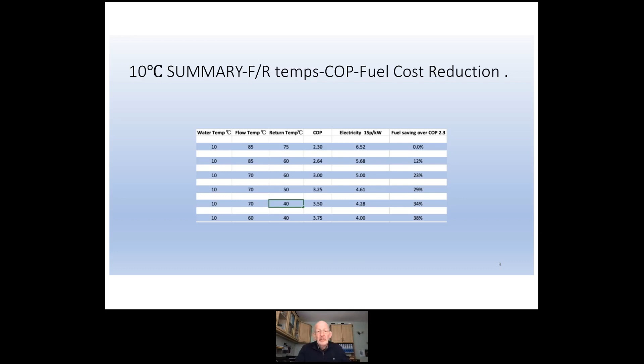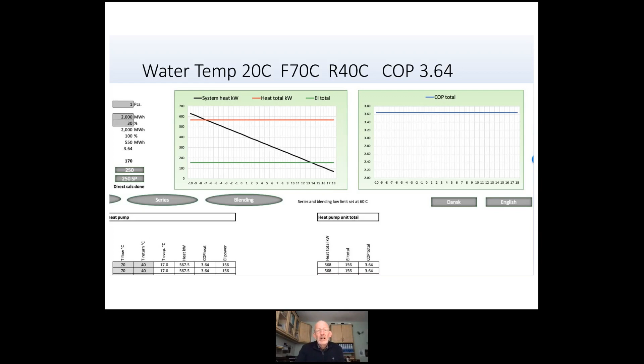Just to show the impact still of flow and return temperatures, on this slide we've increased the source water to 20 degrees C, and I think there's an overwhelming assumption that this will dramatically increase the efficiency of the heat pump. Well, to be honest, it does increase the efficiency, but it only has marginal effect. The main influence on the efficiency is on the flow and return temperatures.